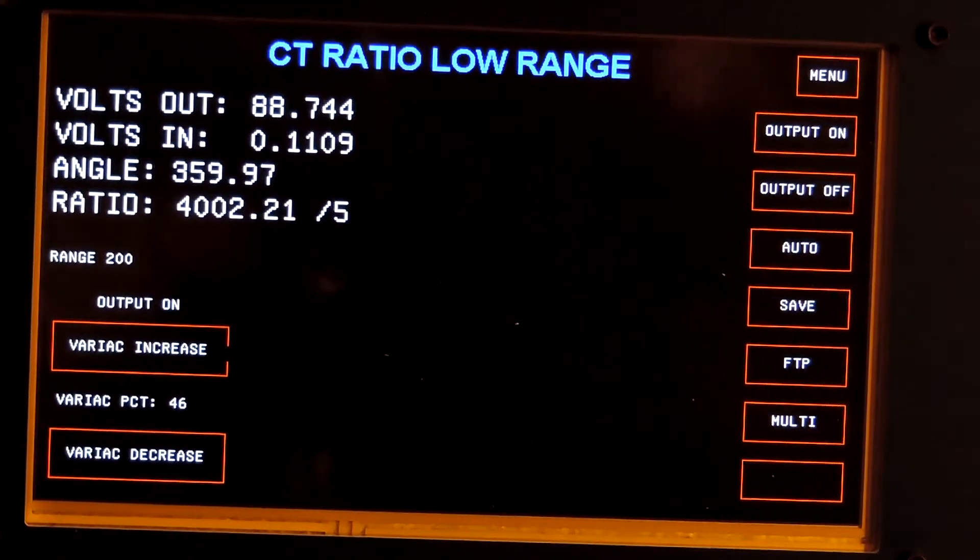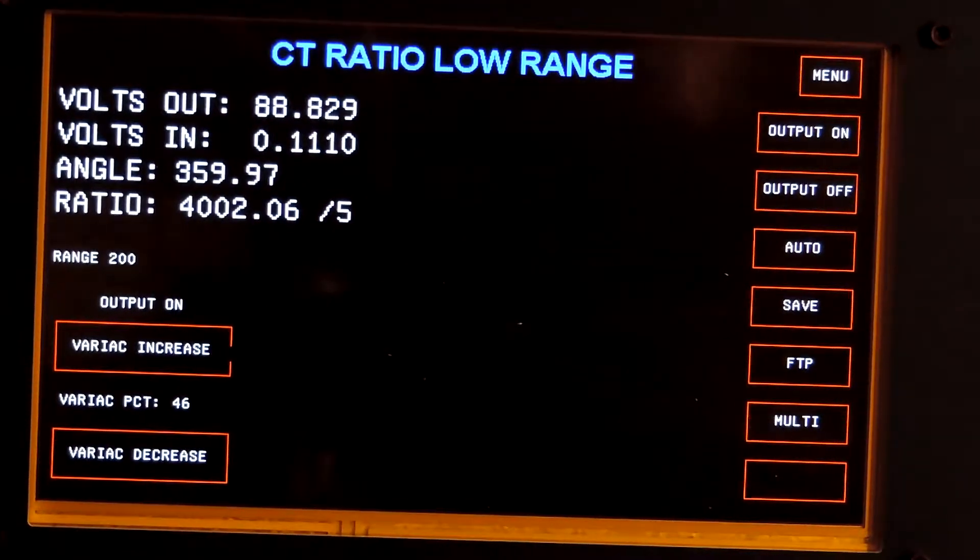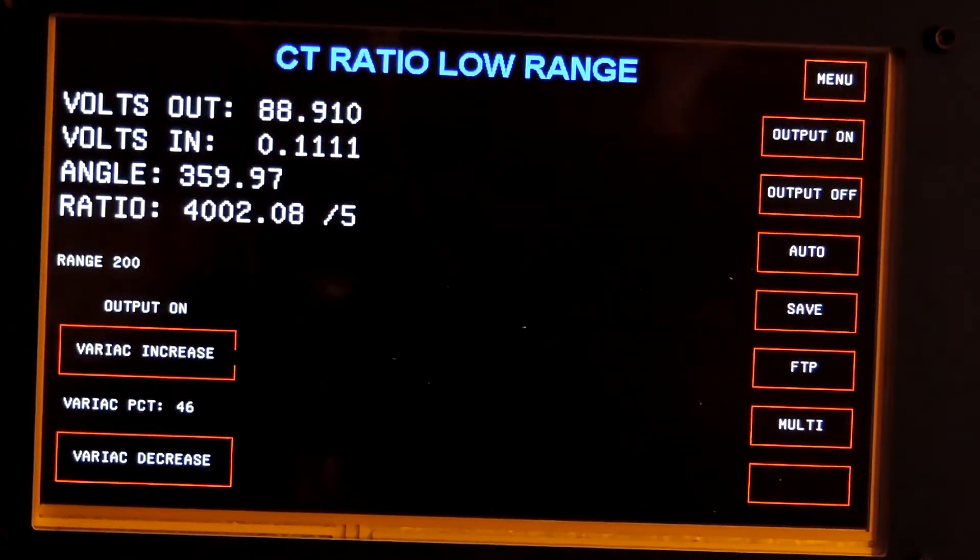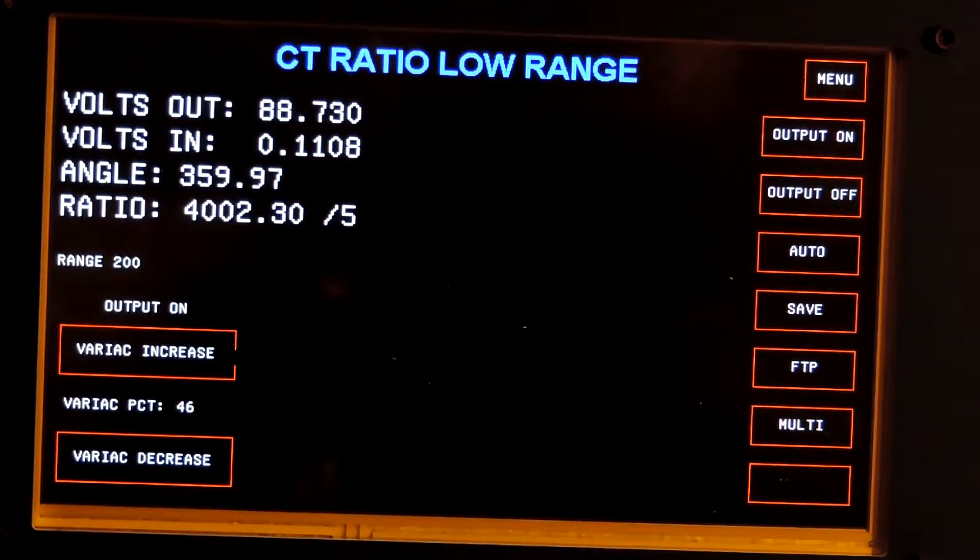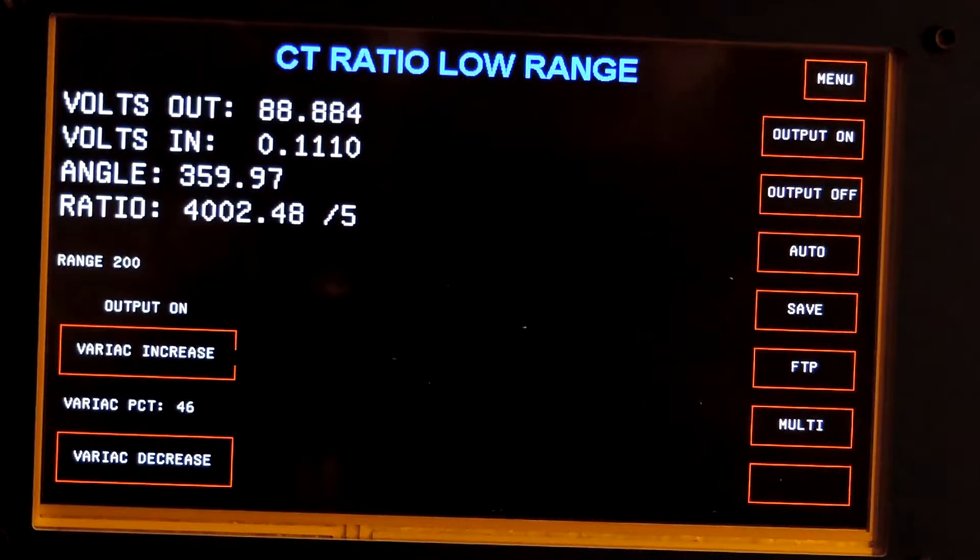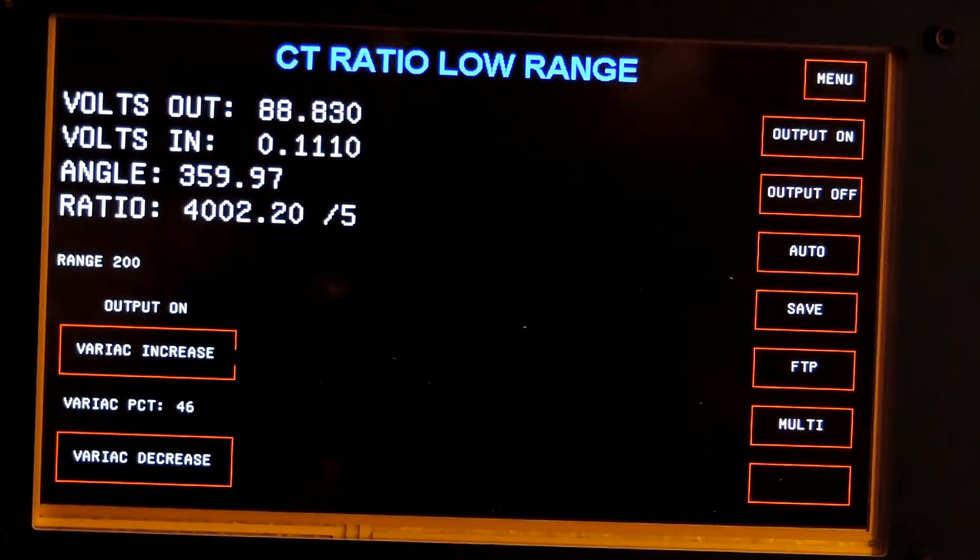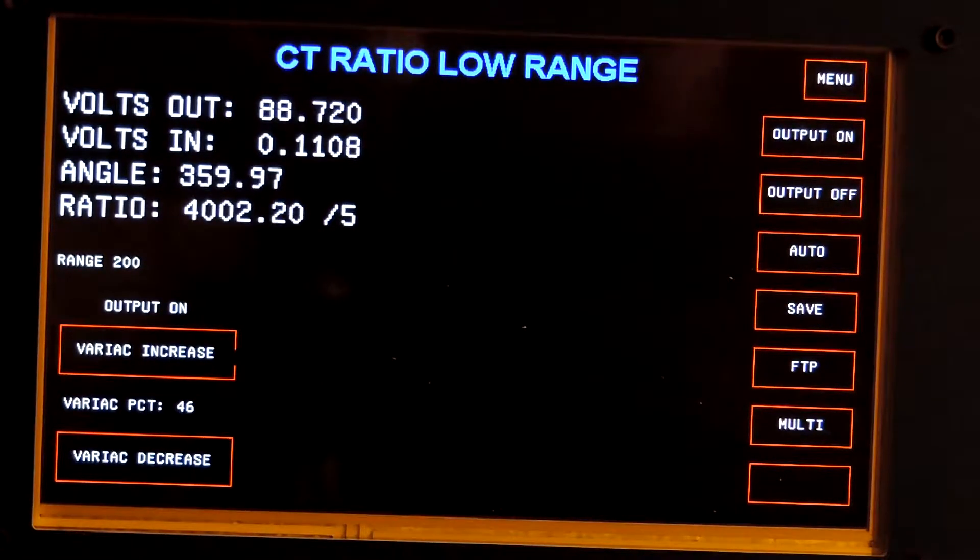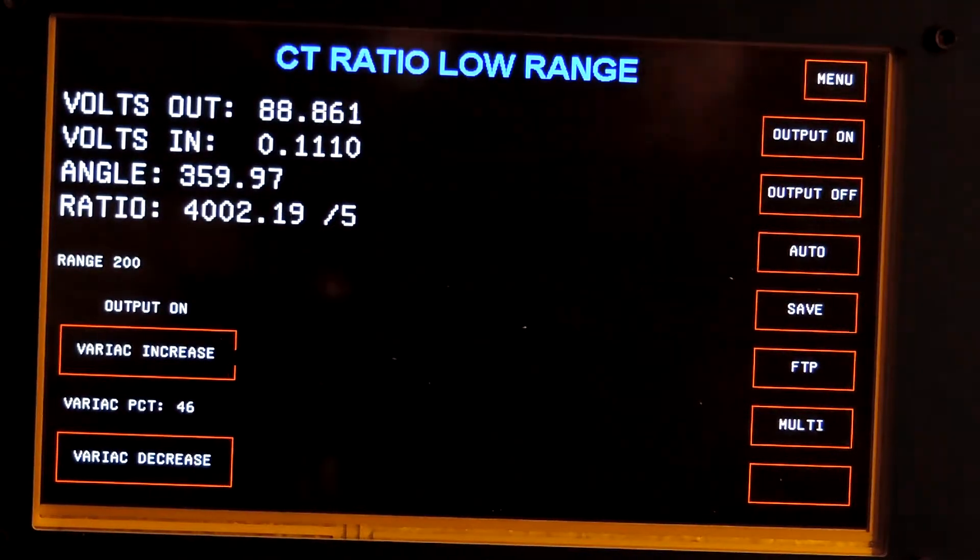You may have seen in the data sheets for some competitive test sets that the higher the CT ratio, the lower the accuracy. They have to bracket their accuracy from a certain ratio to another ratio, and then the next higher ratio is lower accuracy, and so on.